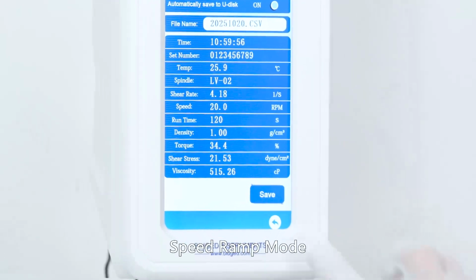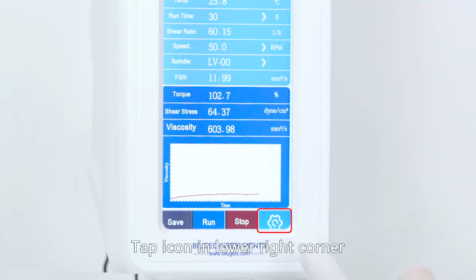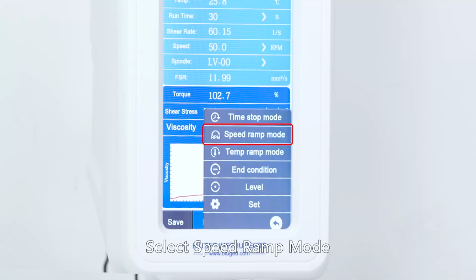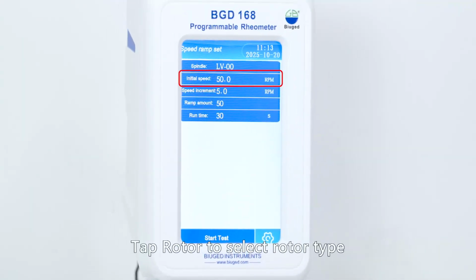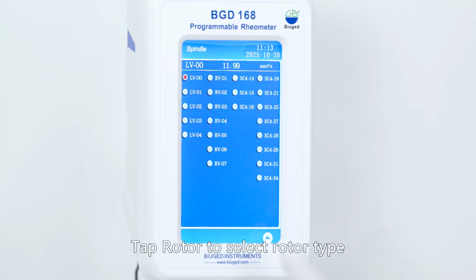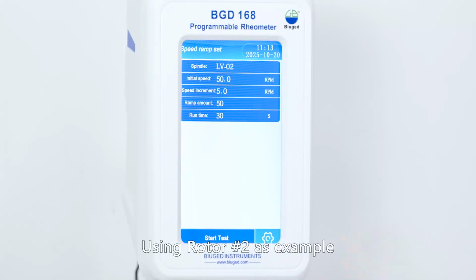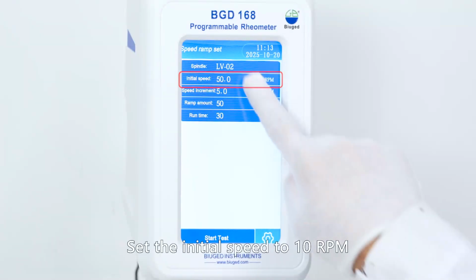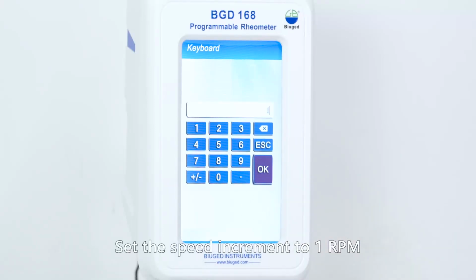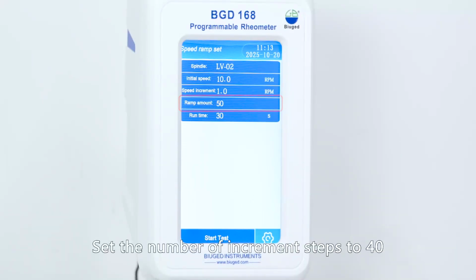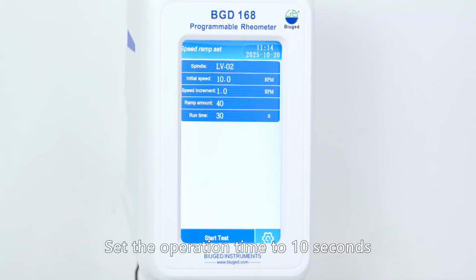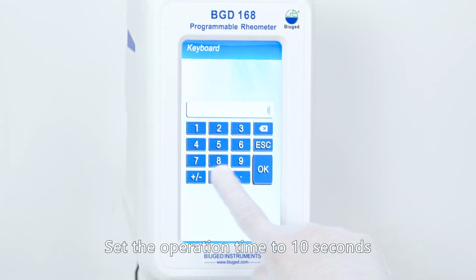Speed ramp mode. Tap icon in lower right corner. Select speed ramp mode. Tap rotor to select rotor type. Using rotor number 2 as example. Set the initial speed to 10 revolutions per minute. Set the speed increment to 1 revolution per minute. Set the number of increment steps to 40. Set the operation time to 10 seconds.